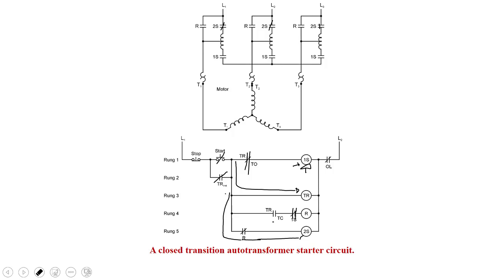So for this brief period in time, during this transition, we still have a path through the auto transformer, half of the auto transformer winding, to get to the motor. All right, what's the next thing that happens after that? If 1S de-energizes, all right, so that's the end of that.